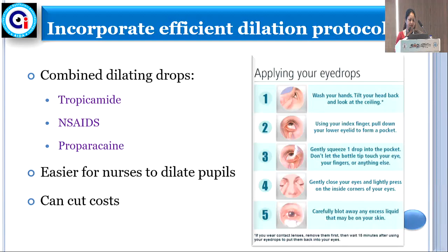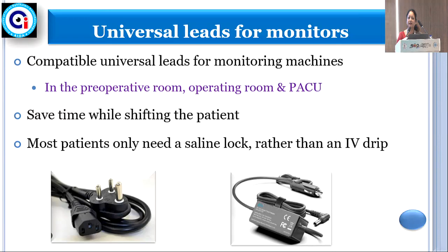Universal lead wires for monitors are also available, so they should be kept in the pre-operating room, operating room, and the PACU, so that once you are shifting the machine or monitor, you can shift only the machine or monitor, and you have the universal lead there. It is not needed in every patient to put the IV drip. You can put the IV line and put a saline lock, so that the patient can be shifted in lesser time. Then smart OT equipment is also available. OT table with remote, with memory. So it is memory 1, 2, 3.